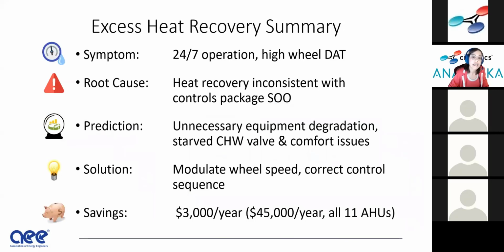So the symptom here, high heat wheel DAT and 24/7 operation. This was inconsistent with the sequence of operations, which showed different periods that it should be modulating and shutting down, et cetera. This can lead to equipment degradation. It's running when it shouldn't be all the time, flat out. So you could actually have equipment failure sooner than intended, sooner than all of these design documents estimate, right? You can have a starved chilled water valve because you're introducing so much excess heat that your system wasn't rated to handle that, to cool that back down to set point. You can have comfort issues, therefore. So here you want to correct the control sequence, make sure that wheel is modulating. If it has a VFD, you can install one on it if it doesn't.